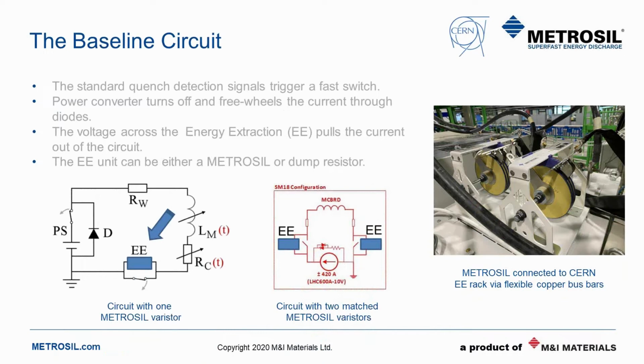Now, sometimes we need to extract more energy, which would mean more voltage. In this particular case, the voltage for the circuit in the CERN power supply was limited. So we used two matched METROSILs, putting earth in the center, so we could extract twice the energy and yet still maintain the voltage to ground. On the right hand side you see a photograph of the two METROSIL units. They were just connected via copper braids to the positions, the terminals where we would have connected the normal dump resistor.